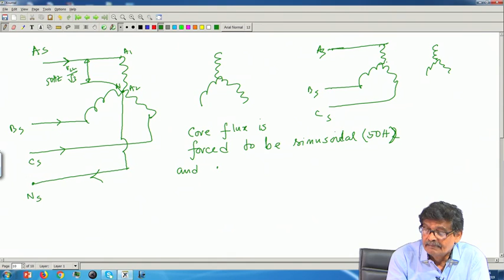Therefore, in this case flux is forced to be sinusoidal with 50 hertz and magnetizing current then must have both 50 hertz plus 150 hertz component. Is it possible? Answer is yes. Because of what? Third harmonic current will find its return path via this.